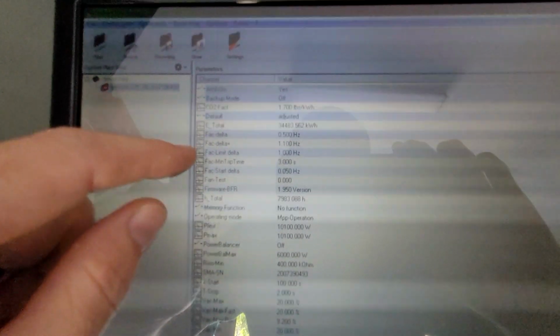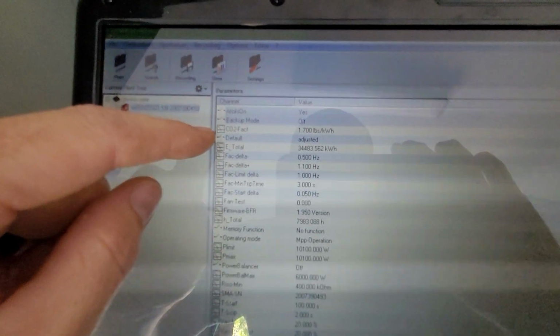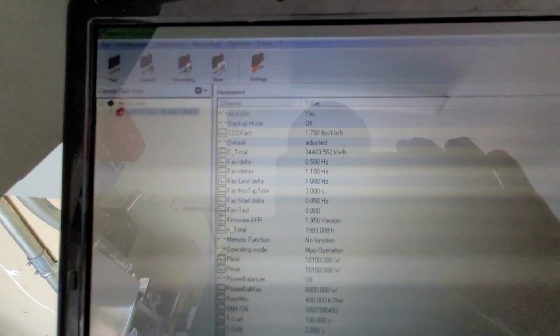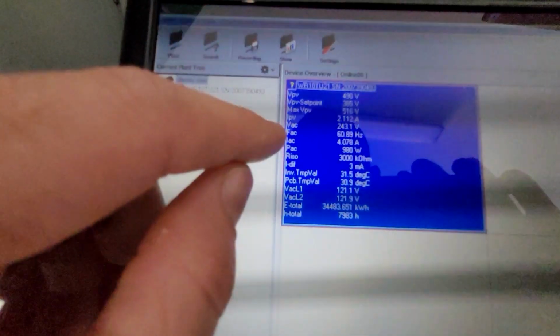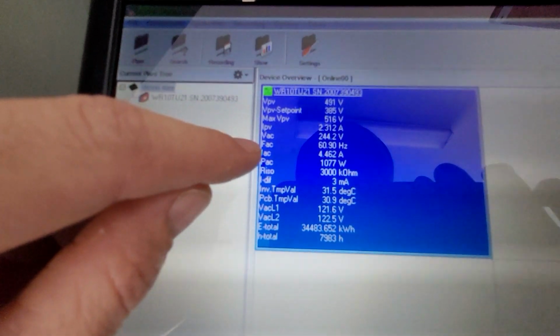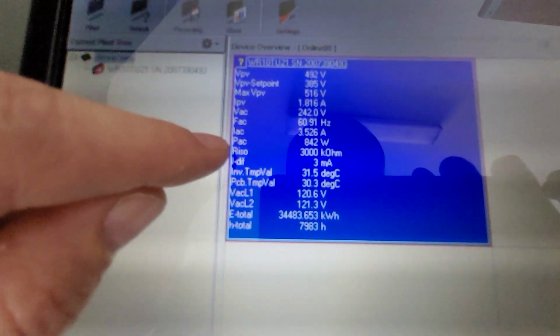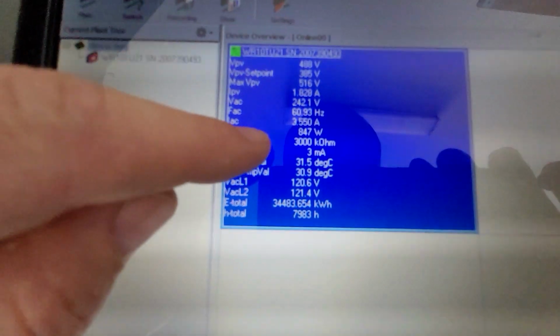The FAC, delta minus, delta plus, the limit delta, and the start delta are all important ones that need to be narrowed down from the factory settings. And it's not in backup mode, it's in adjusted, right? Because from the default mode, it's not in off-grid. So we'll go down to show you the values.